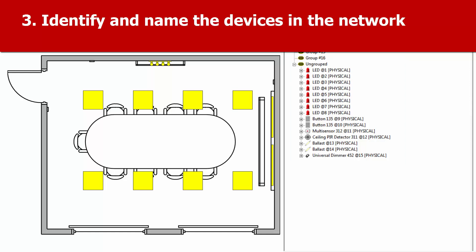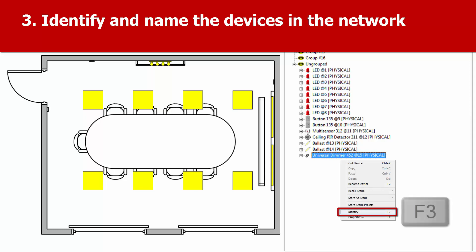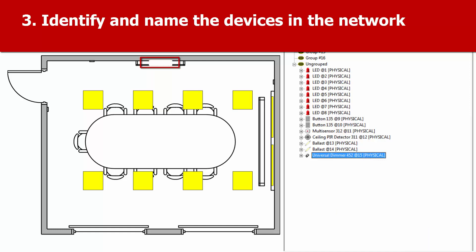First, we need to identify which DALI devices are controlling which lamps. Select a DALI device in Toolbox and right-click Identify, or press F3. The lamps connected to the DALI device will begin to flash. Now you can see which DALI device it is, rename it in Toolbox.